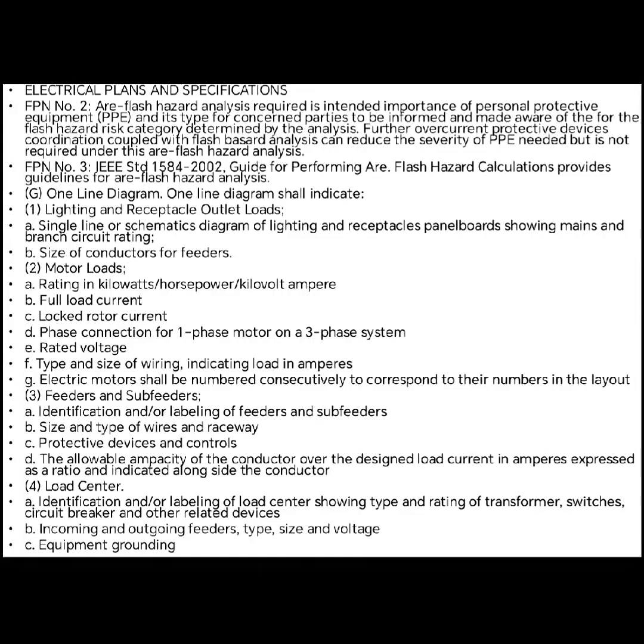The one-line diagram shall indicate lighting and receptacle outlet loads. A single line schematic diagram of lighting and receptacle panel boards shows the mains and the branch circuit ratings, and the size of conductors for feeders. Motor loads: rating in kilowatts, horsepower, kilovolt-ampere, full load current, locked rotor motor current, phase connections for a single-phase motor on a three-phase system, rated voltage, type and size of wiring, indicating load amperes. Electric motors shall be numbered consecutively to correspond to their numbers in the layout.